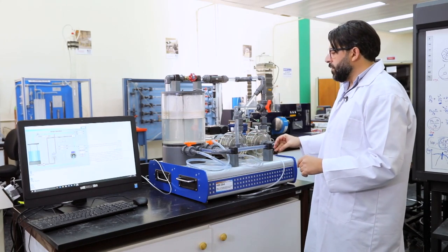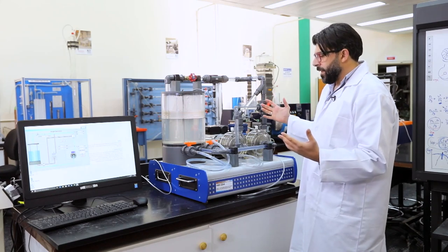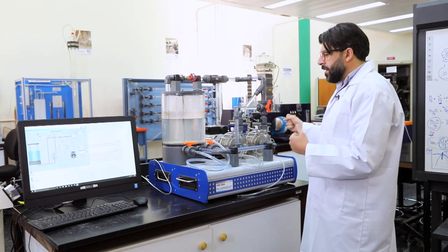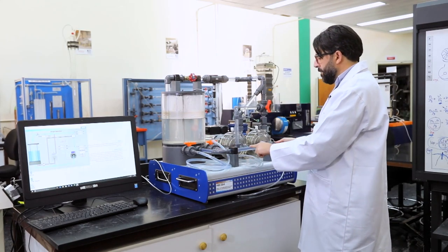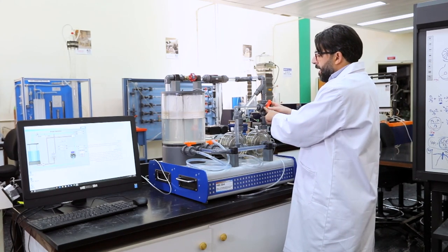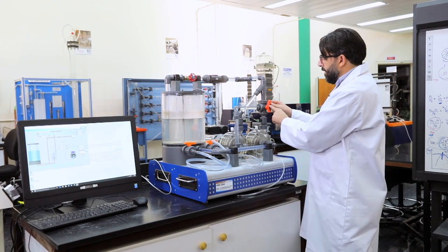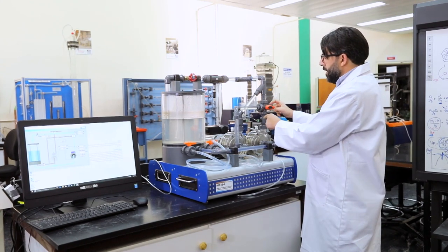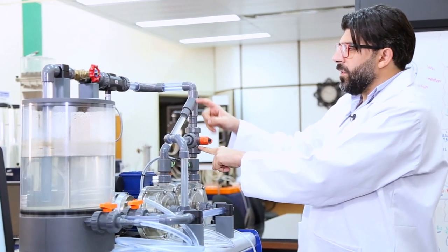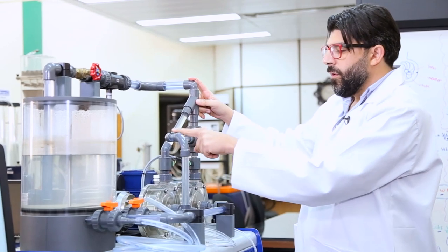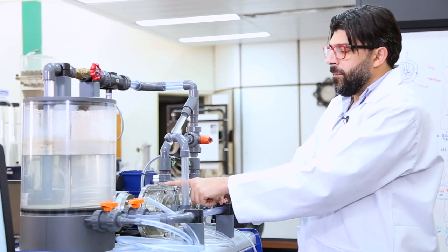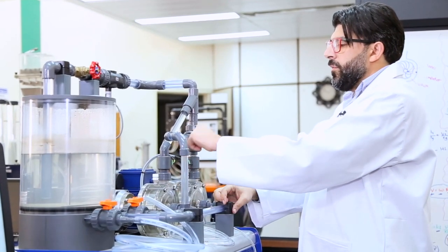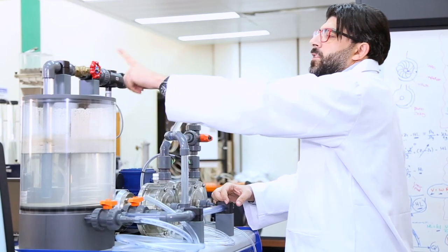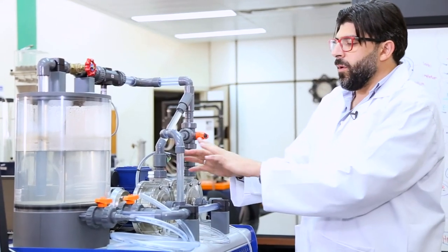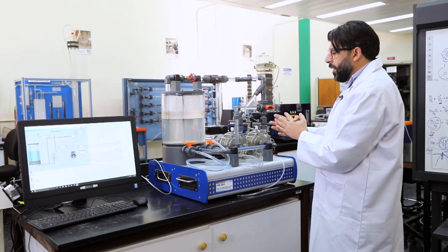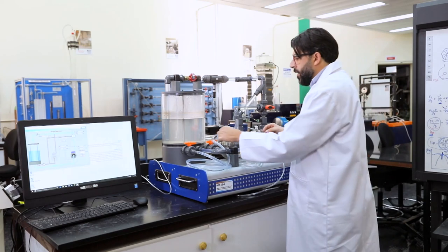So if I want to make my system in series, in series means the water is taken from the first pump, exits here, then I have to connect it to the second pump. So now, the valve here is closed, so I will open it this way. That means the water will not continue up. It is forced to go to the second pump. The second pump will push the water from here until it goes to the tank again, and the flow rate is measured. So this setup is for two pumps in series. If I want to make two pumps in parallel, I have to open this valve.